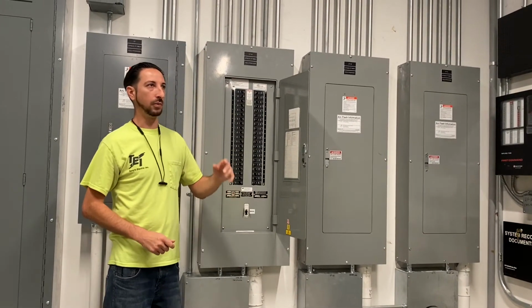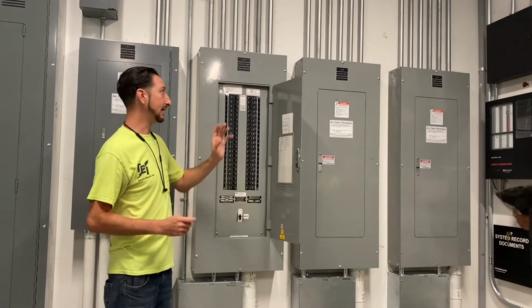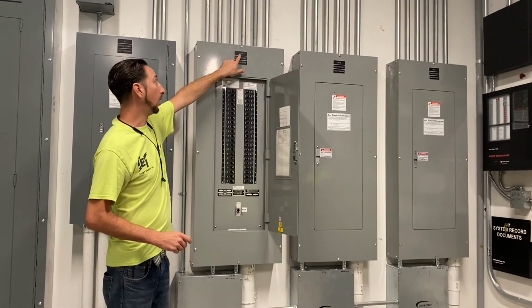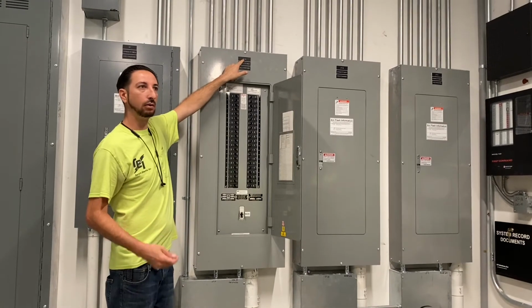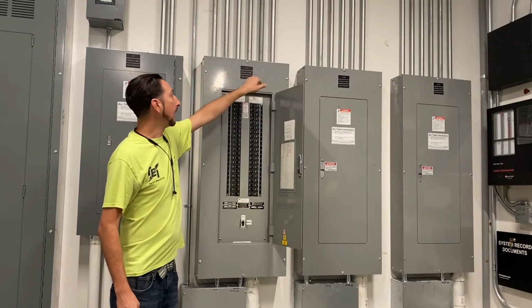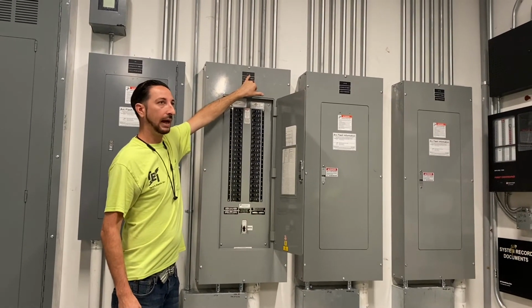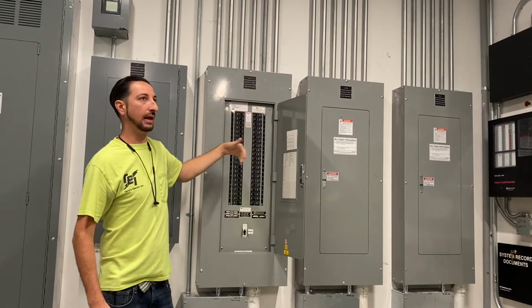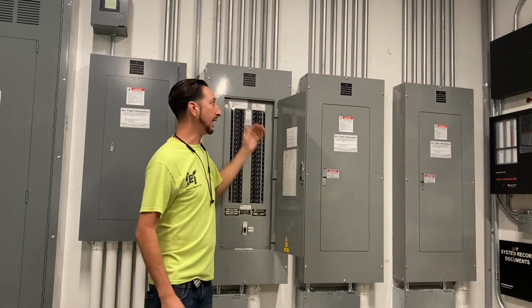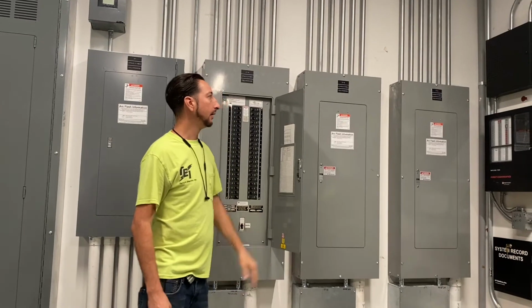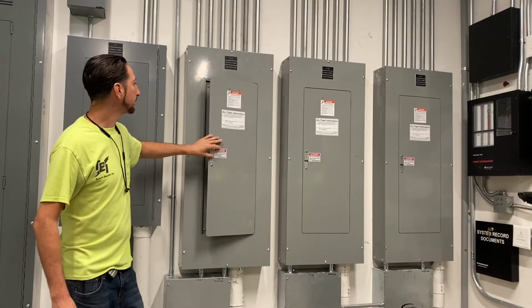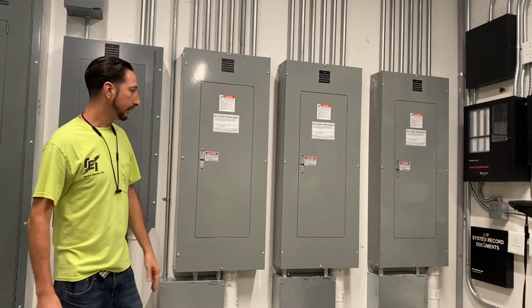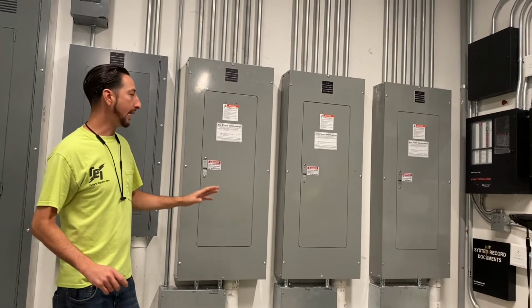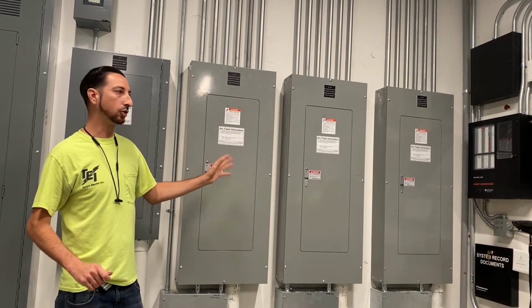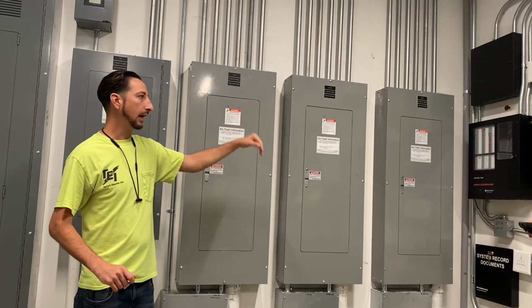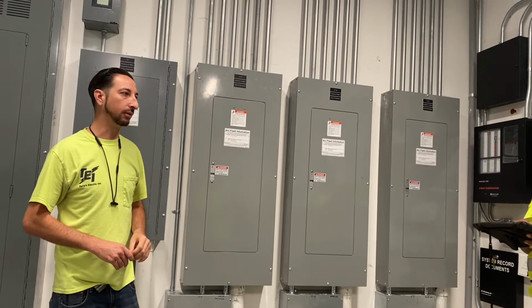So you'll have to read the schedule on anything that's not an LP. LP stands for lighting panel, and you have 1A, and 1 stands for first floor, and then A is just a symbol of how many are in the chain there. So you got A, B, and C. And so on the first floor, you have 4 lighting control panels. You have 3 here, and then you have a 4th one over by conference, and we'll visit that one.